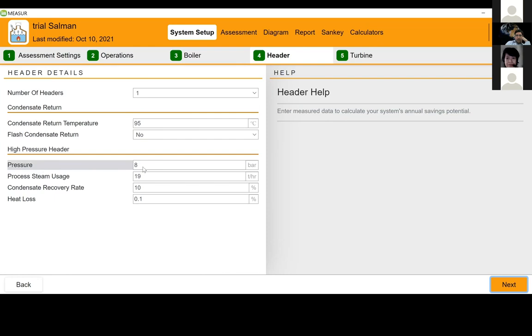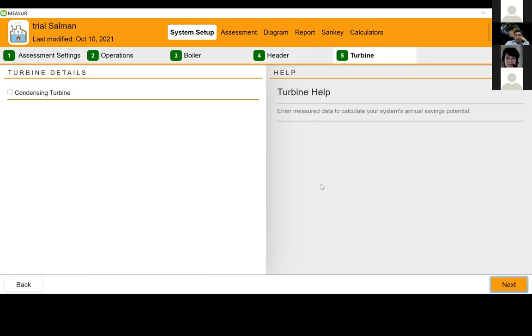Then the pressure of the high pressure header was 8 bar. Process steam usage was 19 ton per hour. Condensate recovery rate was 10% only in this case, and heat loss in the header. So the temperature difference in percentage from inlet of the header and outlet of the main header was 0.1%. You can also take help here in how to calculate these things generally. Then turbine, so this boiler did not have a condensing turbine to power energy. So this I unchecked and I moved forward.